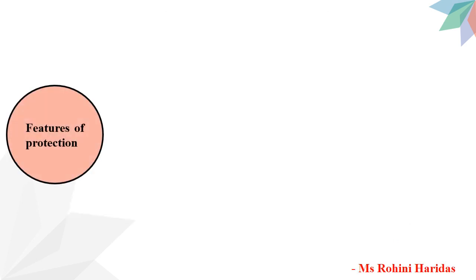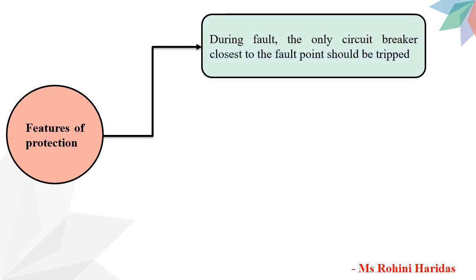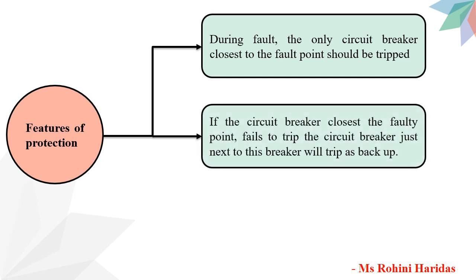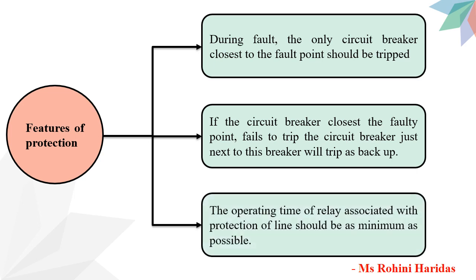Now let us see the features of protection. The first one is: during a fault, only the circuit breaker closest to the fault point should be tripped, meaning all other circuit breakers should remain closed to achieve selectivity. Next, if the circuit breaker closest to the faulty point fails to trip, the circuit breaker just next to it will trip as backup protection. Third, the operating time of the relay should be as minimum as possible in order to preserve system stability.